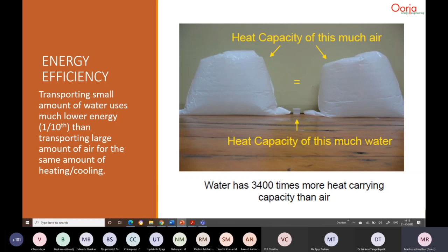This is data from one of our projects in Chennai, where in the same room, for delivering roughly the same cooling load, which is somewhere between 11 and 12 tons of cooling, here we have mentioned in kilowatt thermal, translating to 11 to 12 tons of cooling, an air handling unit is consuming about 6.7 kilowatts, basically the fan motor. Whereas the pump that distributes the cold water in the radiant circuits is using only 0.4 kilowatt. So this is the big difference in the distribution energy that is required.